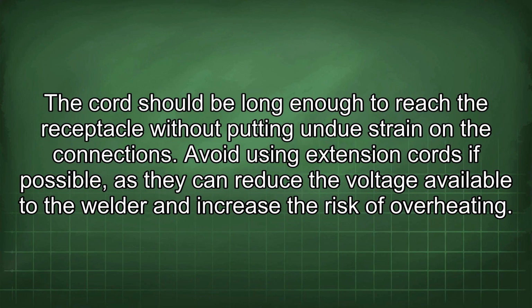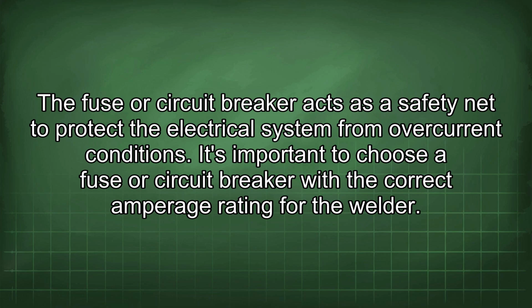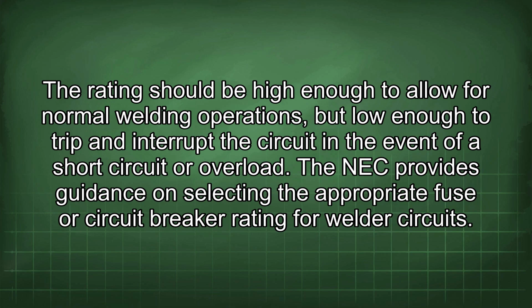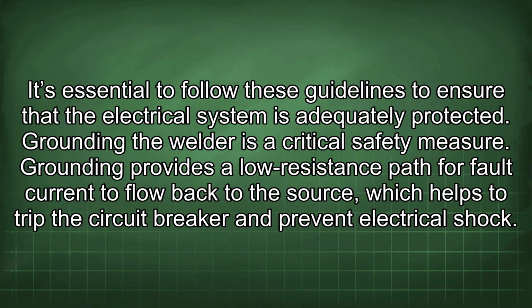of overheating. The fuse or circuit breaker acts as a safety net to protect the electrical system from overcurrent conditions. It's important to choose a fuse or circuit breaker with the correct amperage rating for the welder. The rating should be high enough to allow for normal welding operations, but low enough to trip and interrupt the circuit in the event of a short circuit or overload. The NEC provides guidance on selecting the appropriate fuse or circuit breaker rating for welder circuits. It's essential to follow these guidelines to ensure that the electrical system is adequately protected.